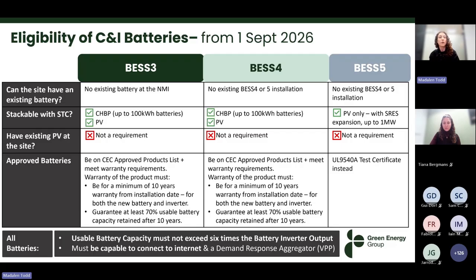If you're concerned about any of the batteries you're intending to use and install under this scheme, I recommend that you reach out to us and we can check the warranties for you to ensure that they meet those requirements. Lastly, for BESS 5, the approved products list is still to be confirmed at this stage. We are expecting a rule change and a new method guide from the regulator any day now. And there are no warranty requirements from the rule, so just your normal requirements and warranties will apply. Your battery just has to have a test certificate from your manufacturer. So please do make sure that you obtain this for any installs that you plan to do under BESS 5.